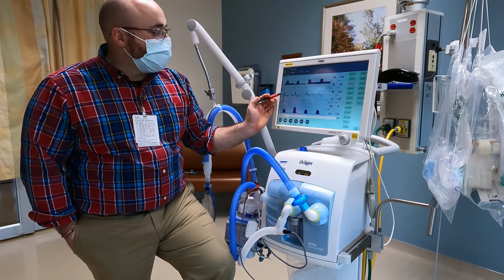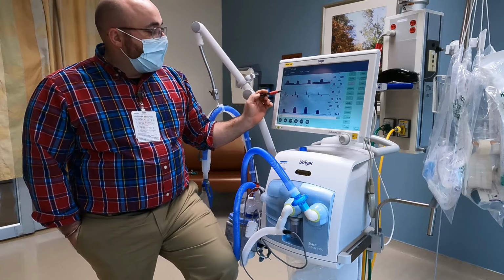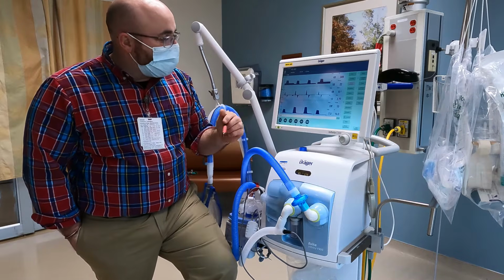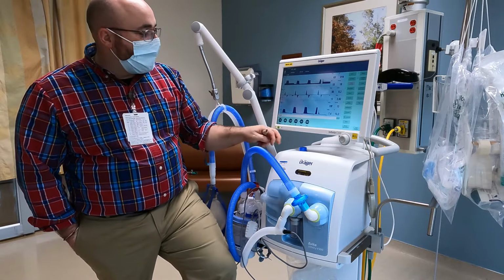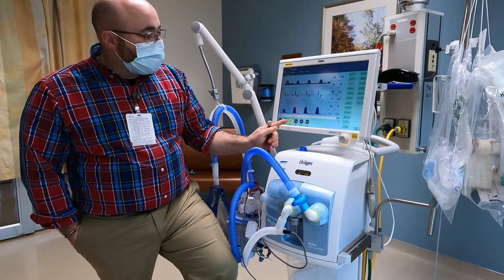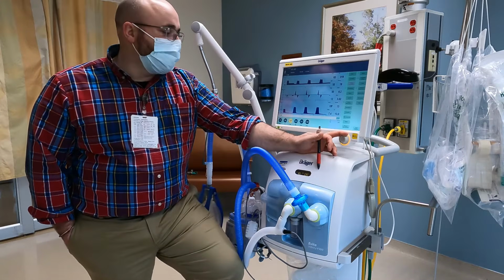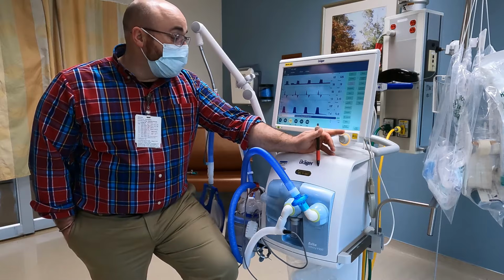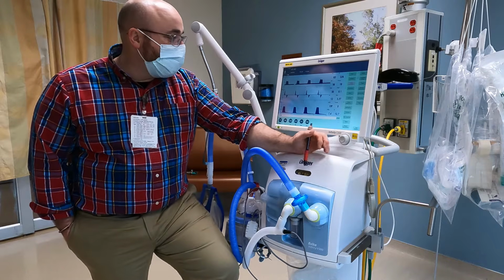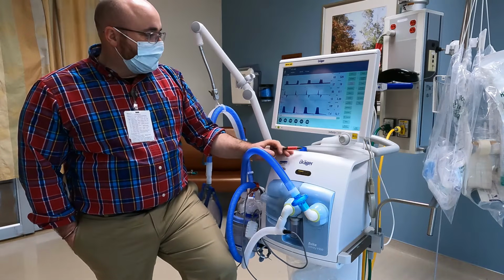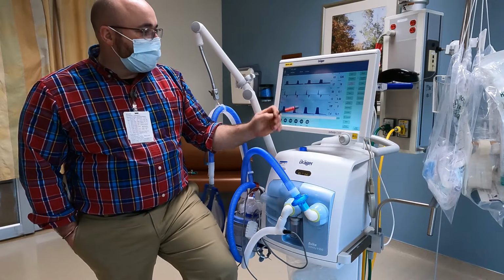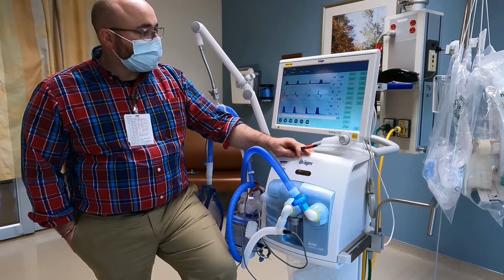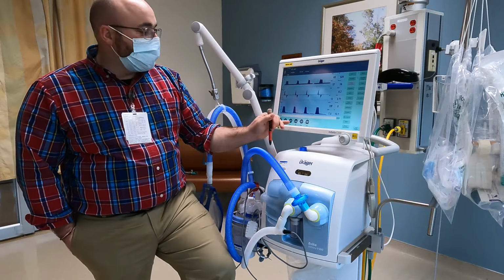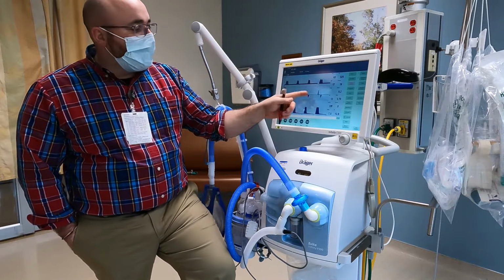This is our flow. So this is the air going in, and then there's the air as it exhales. So it goes in, it holds, and it exhales. And why does it hold? It's because this TI is set too high now. This is nothing you need to know, but that's inspiratory time. So if I turn that down, this will be a little tighter together. So it just doesn't hold it quite as long. And there's the expiratory side.